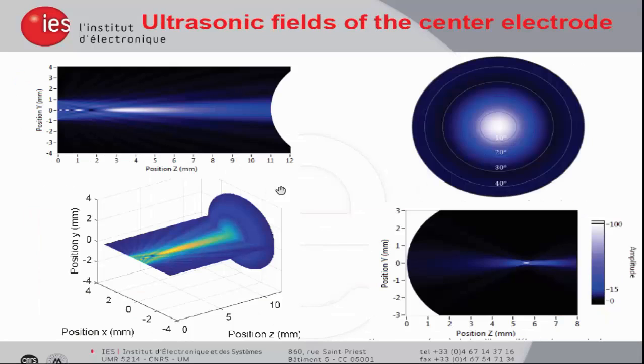These elements will radiate differently. Here you've got an image of the radiation field in the silica delay line for the central element. So you see a collimated field that will insonify the acoustic lens here at its center. So this field is being radiated into the coupling medium and is focused at a position between 5 and 6 millimeters away from the sensor.